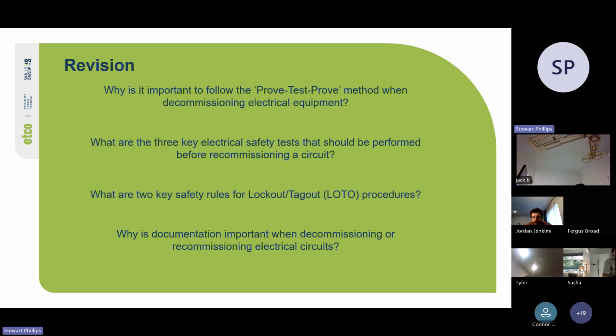The main reasons are it's a way for us to ensure the circuit is completely de-energized before work begins, and it prevents false readings due to faulty testers or incorrect assumptions. Sometimes, even though you've isolated the circuit, there will still be some residual voltage, especially if other machines are connected.